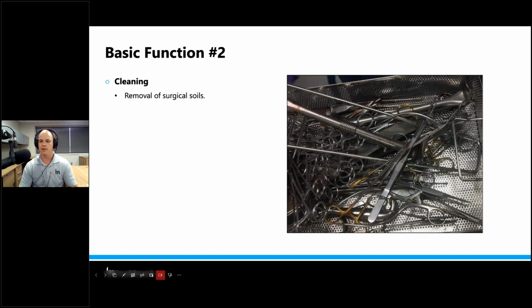So I show you here, there's a detergent pump. What's unique here is that there's only one detergent pump, and it feeds both sides of the ultrasonic unit. So you can see this is what I would refer to as a double-sided or dual basin ultrasonic unit, and it has one pump that sends detergent to both sides, okay? I'm agnostic to whether or not that is good or bad. It's just something to understand.